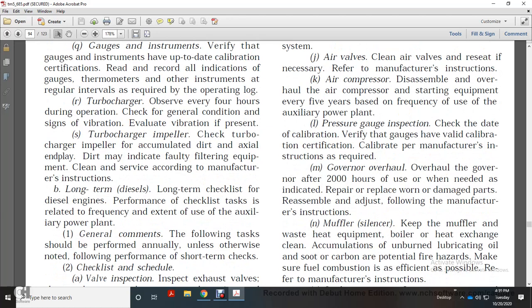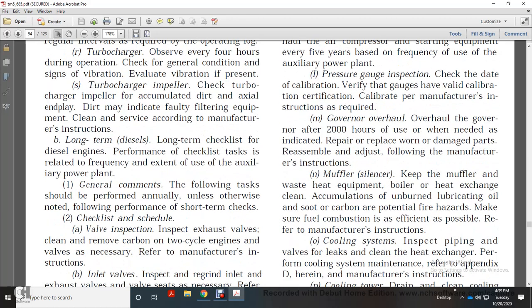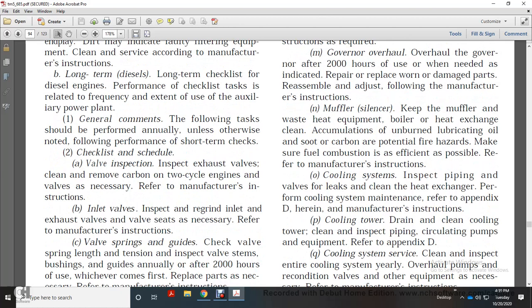Governor: overhaul the governor after 2,000 hours. Repair or replace worn and damaged parts, reassemble, and adjust following the manufacturer's instructions. Muffler and silencer: keep the muffler, waste heat equipment, boiler, and heat exchanger clean of accumulated unburned lubricating oil and carbon, which are a potential fire hazard, to make sure fuel combustion is as efficient as possible. Refer to the manufacturer's instructions.